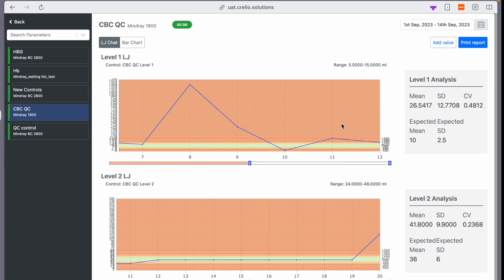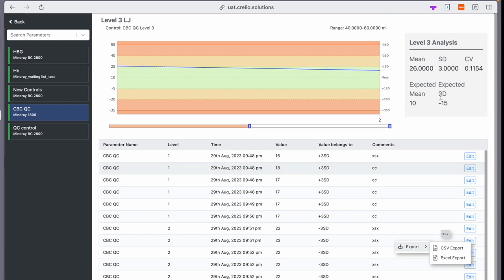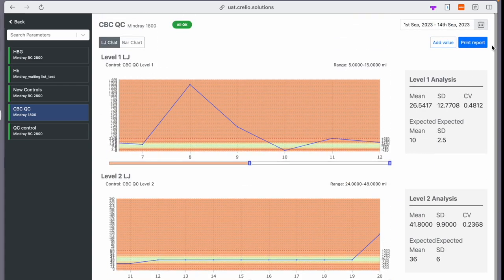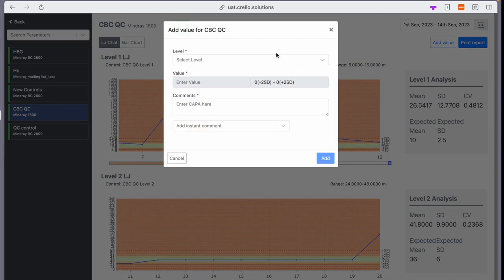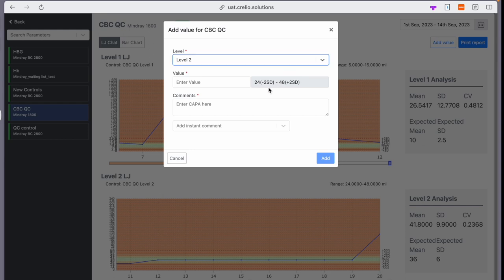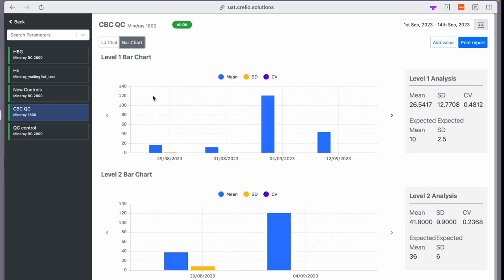Next to the graph, you can also print the report if you want to keep records, or you can just export the values in Excel. From here, you can also add control values manually if there is manual QC recording which you want to record. You can also see the bar chart of the QC values over time to see any shift in patterns.